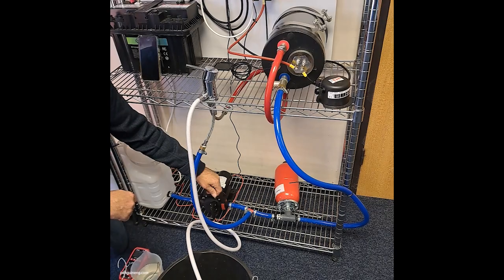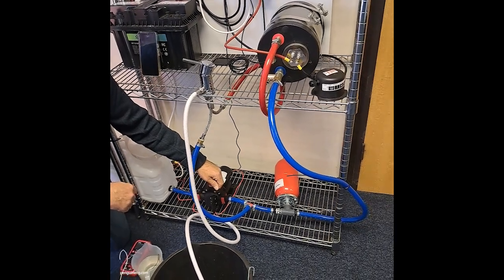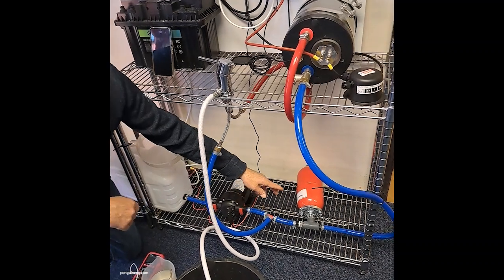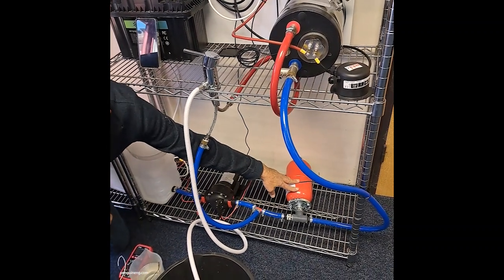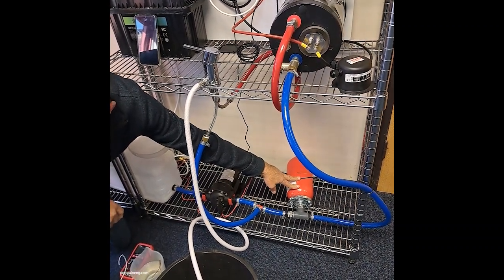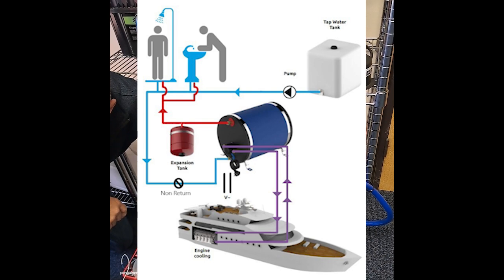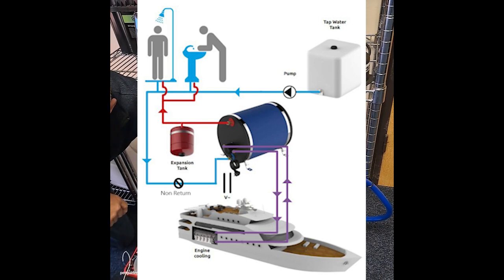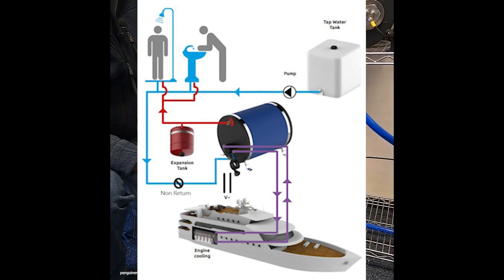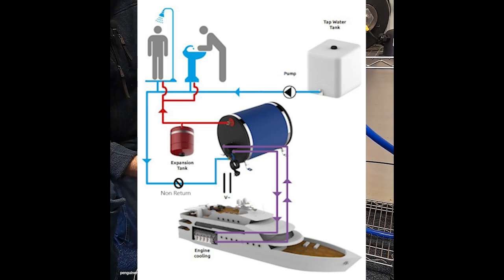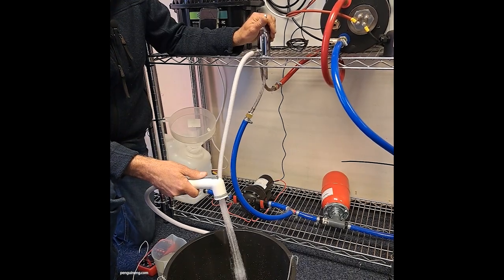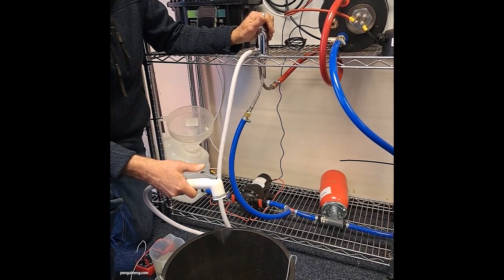As we mentioned earlier, the accumulator helps to maintain a consistent pressure to stop the pump rapidly switching on and off. The accumulator on this setup is on the hot side of the water circuit. On cold, without the aid of the accumulator, you can see the pulsing. On hot, with the accumulator, the difference is obvious.